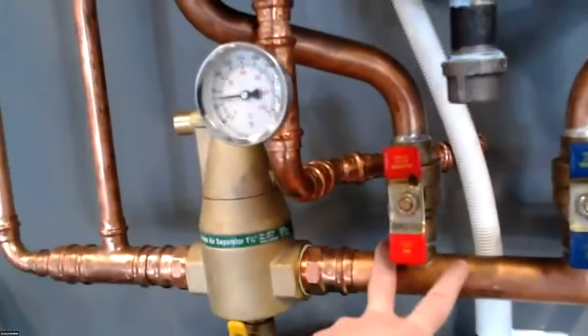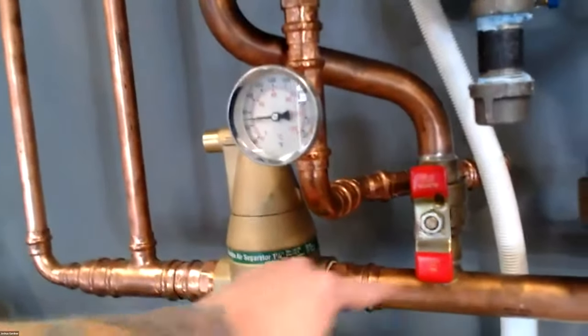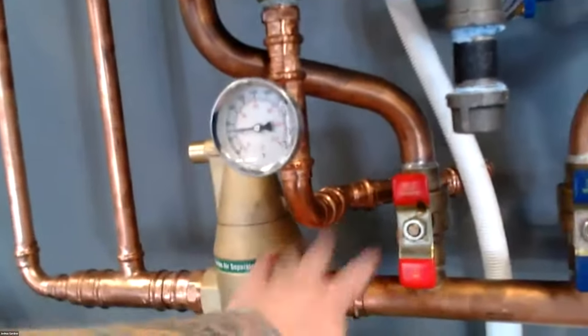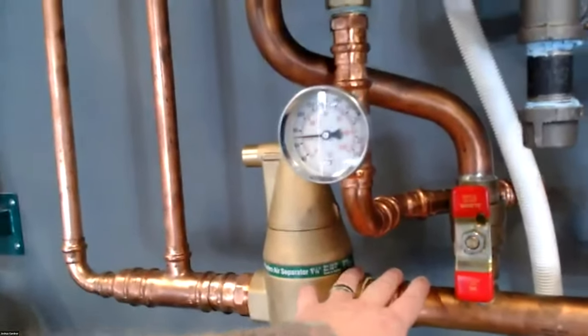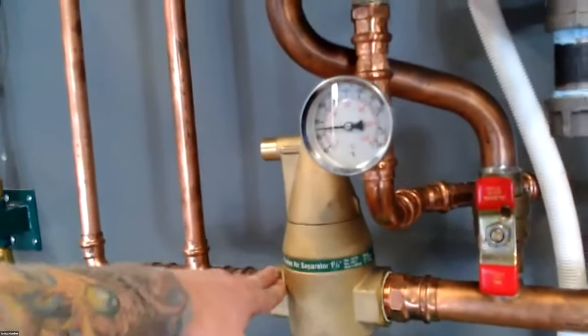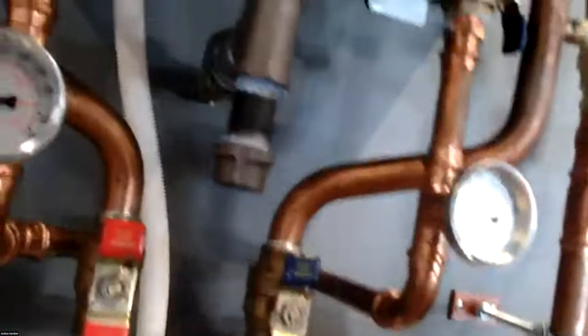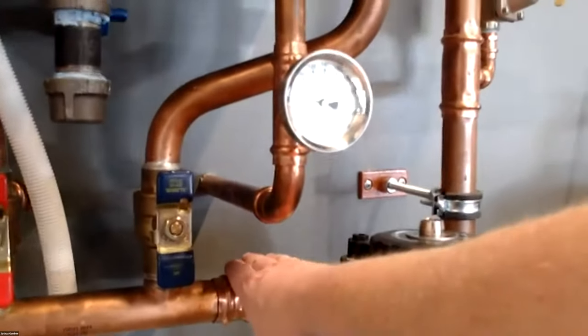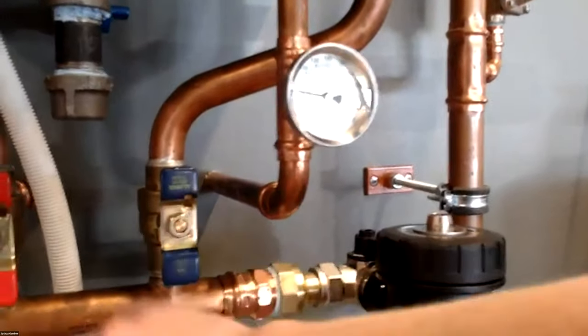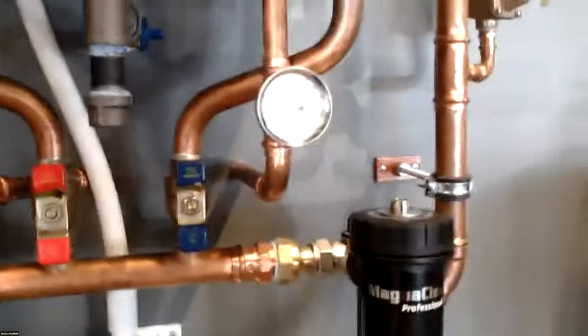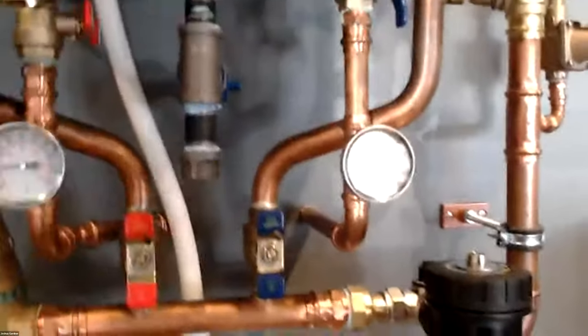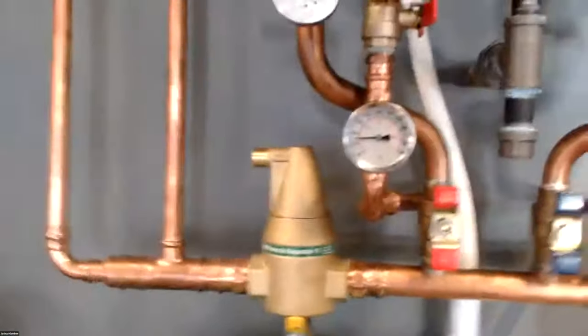Coming off closely spaced tees or a header kit here, I want at least 12 inches into my air separator so that the air can settle in the top of the pipe a little bit and get better air separation. Also, on the closely spaced tees, I want a little bit of separation on my return side. That way, we're not affecting the flow through my primary. So I probably would have left a little bit. I'm tight in this room, the boilers next to each other, so I get why it was done this way.